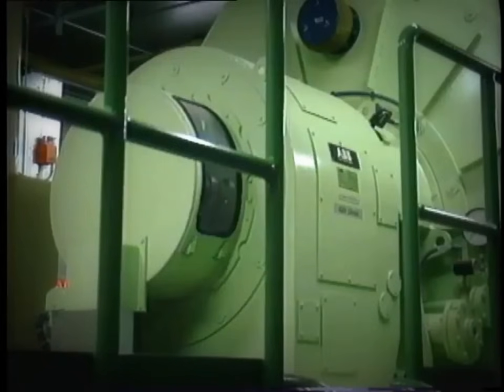Another type of excitation system often used is known as the brushless exciter. The exciter is actually a small AC generator, which is built on the end of the generator shaft instead of collector rings.